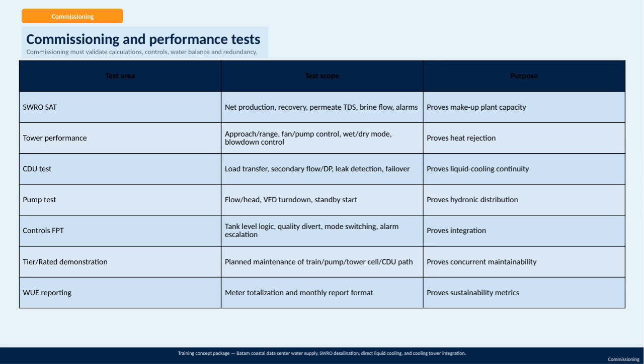Tier and rated demonstrations focus on planned maintenance of critical components like train, pump, tower cell, and CDU path to prove concurrent maintainability. Finally, water use efficiency reporting through meter totalization and monthly reporting helps verify sustainability metrics. Together, these commissioning tests provide comprehensive assurance that all systems perform safely, efficiently, and as designed.